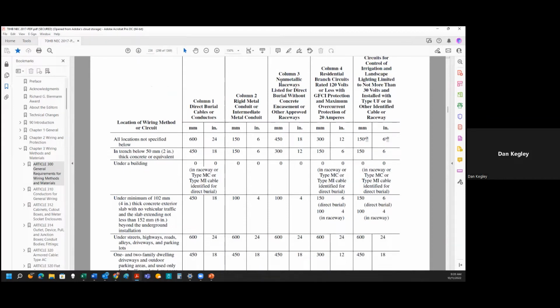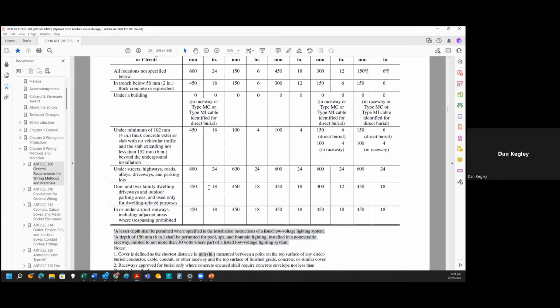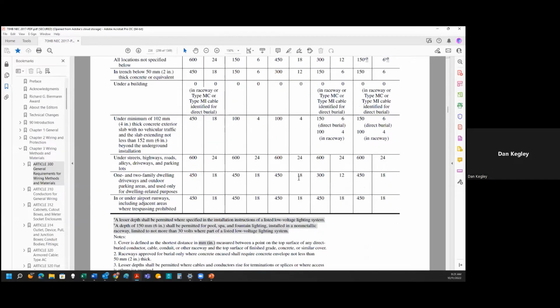If you had PVC, column 3 is non-metallic raceway listed for direct burial without concrete. So that would be your PVC conduits going into the ground without encasement. Here again, 18 inches, 12 inches, 4 inches. But when you get back down to the residential, pretty much any kind of residential scenario, whether you have just the cable, steel, or PVC, it's 18, 18, and 18. So 18 inches is pretty much the magic number if you're at a residential facility with a 1 and 2 family dwelling.